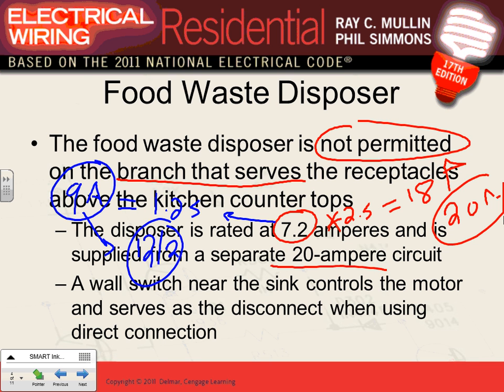So what did we do? We took a 20 amp circuit and we fed our garbage disposal with a 12-2 AWG NM cable. That's what we did. Everybody knows why we went for a 20 amp circuit for these appliances? Almost always, guys, it's first code-wise, and second, it's a very good idea if you have appliances to feed them from a dedicated circuit.